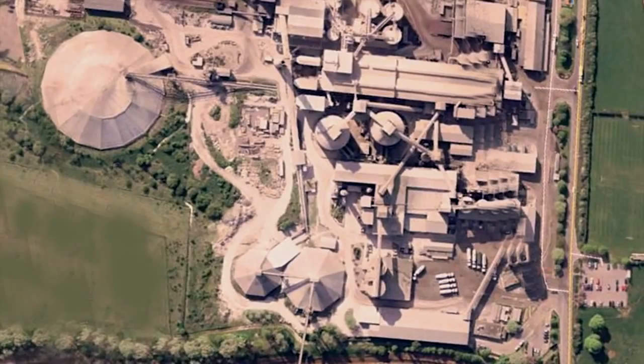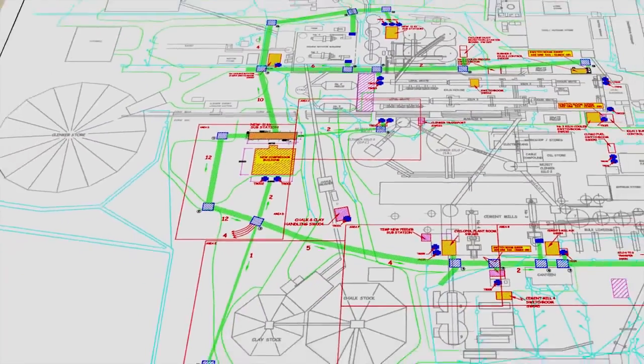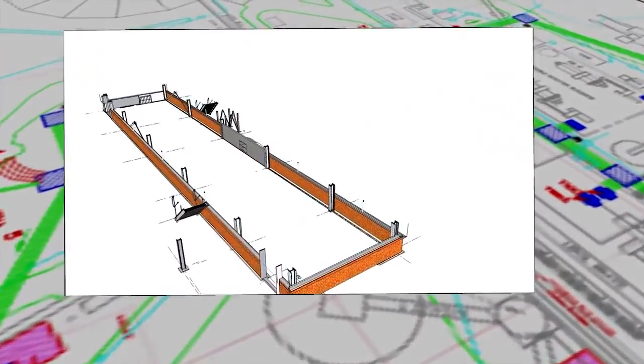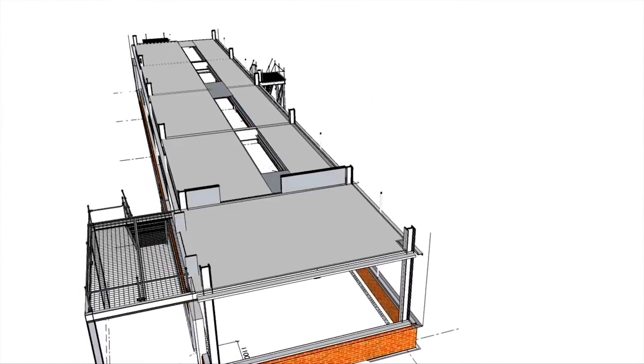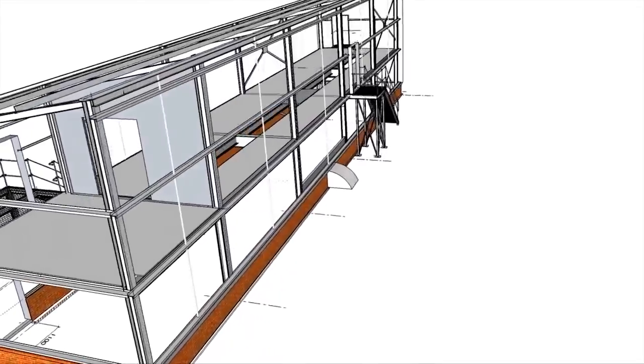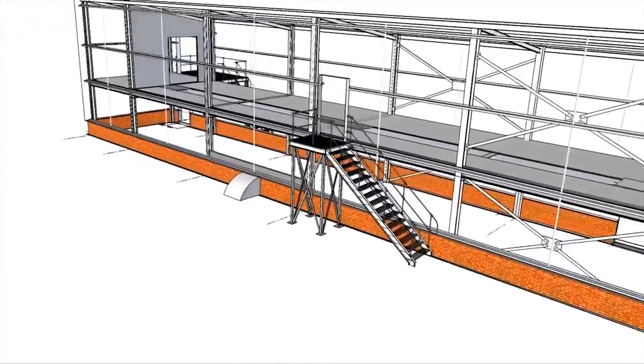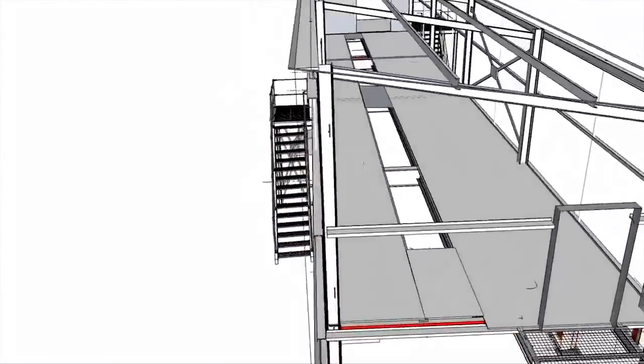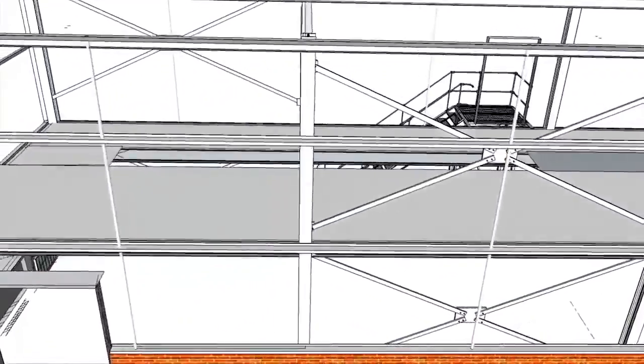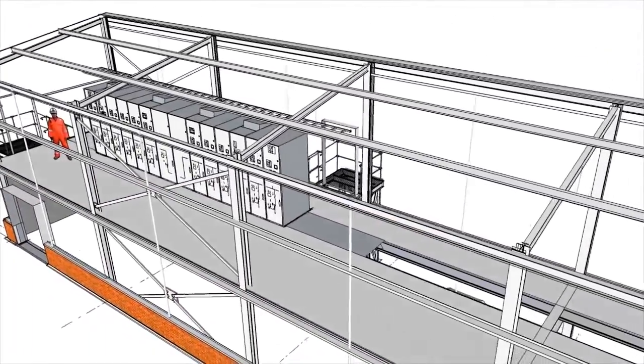ISS was quickly chosen to support the disaster recovery project, which would involve the replacement of primary high voltage and low voltage switchgear associated to power transformers and distribution cabling. It was found that both the primary 11,000 volt intake substations, low voltage 415 volt distribution switchboards, power transformers and over 4 miles of HV cabling were required to be replaced.